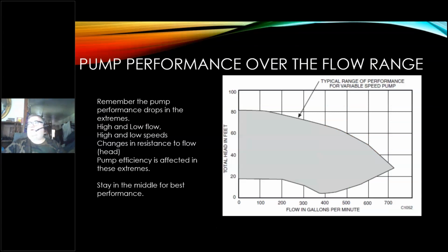Okay, and so this curve actually plots all the possibilities, variable speed, flow. This is what the actual operation of that pump looks like. All the possible permutations for that pump to operate across this entire range of flows and head. Again, they kind of stop at 20 feet in this case, but they'll max you out above 600-700 if you really get to the extreme where you reduce the resistance to flow and speed it up. But high and low flow, high and low speeds, changes in resistance to flow, that's head. Pump efficiency is affected in these extremes.